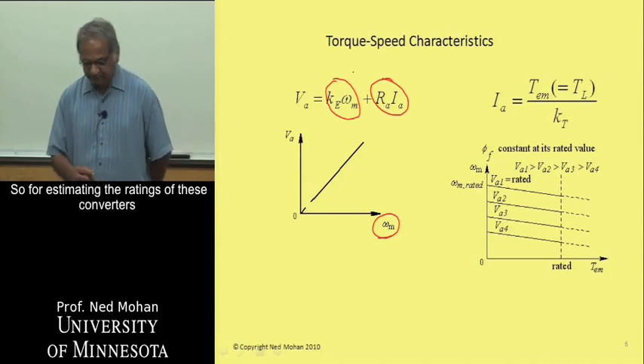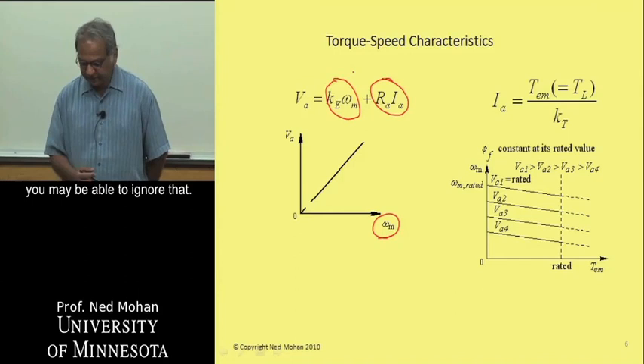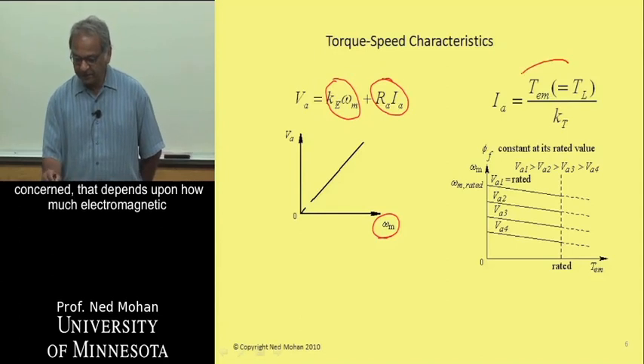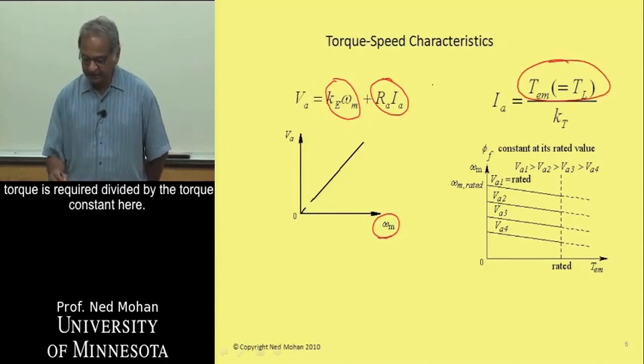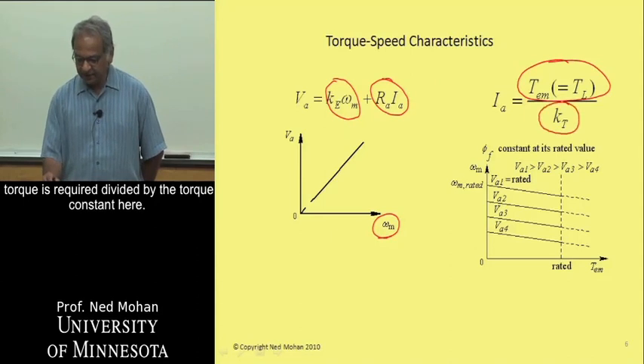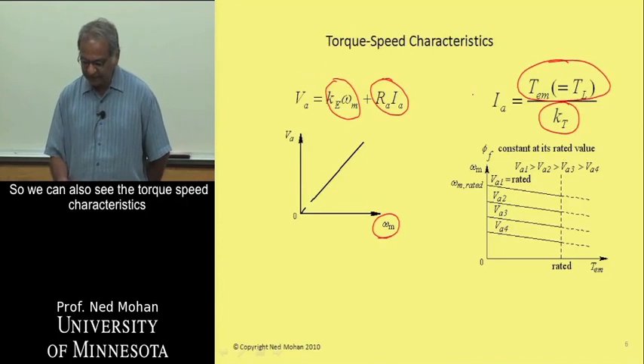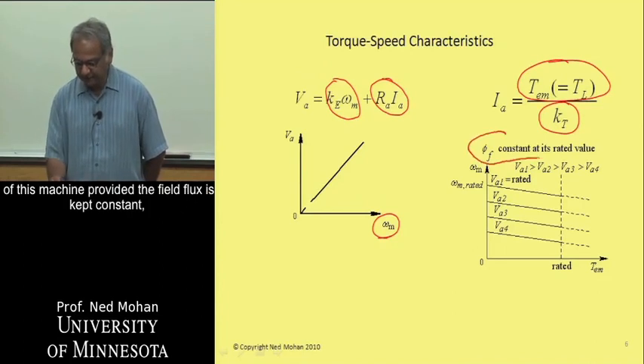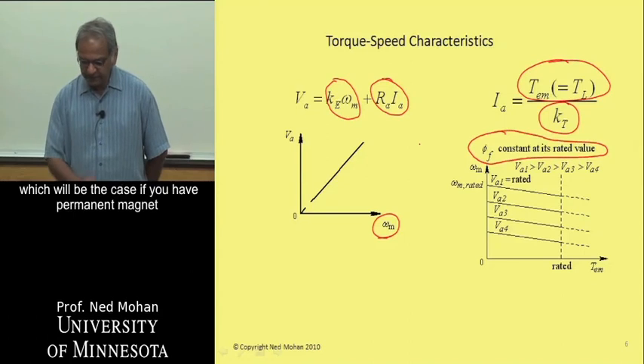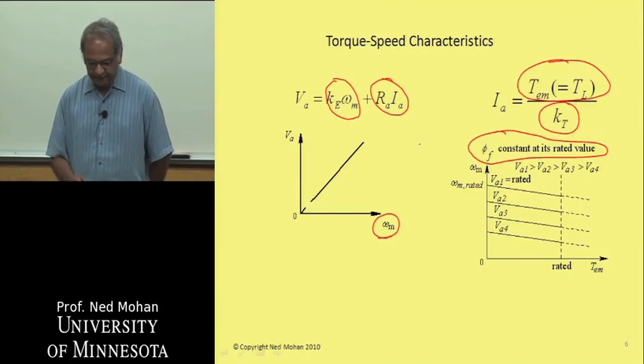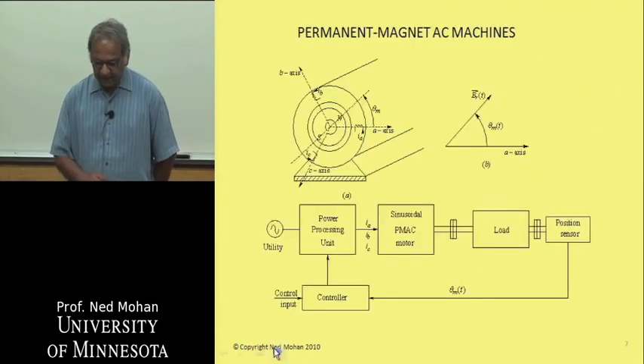So we can see here that the voltage that needs to be there across the armature terminals primarily depends upon the rotational speed. So if you know what the maximum speed is, then we can determine what this term would be, knowing the voltage constant. And then we have to take into account small drop as well across the resistance in steady state, but this is usually pretty small. So for estimating the ratings of these converters, you may be able to ignore that. As far as the current rating of this converter is concerned, that depends upon how much electromagnetic torque is required, divided by the torque constant here. So we can also see the torque speed characteristics of this machine, provided the field flux is kept constant, which will be the case if we have permanent magnet machines, and we are not doing any field weakening.